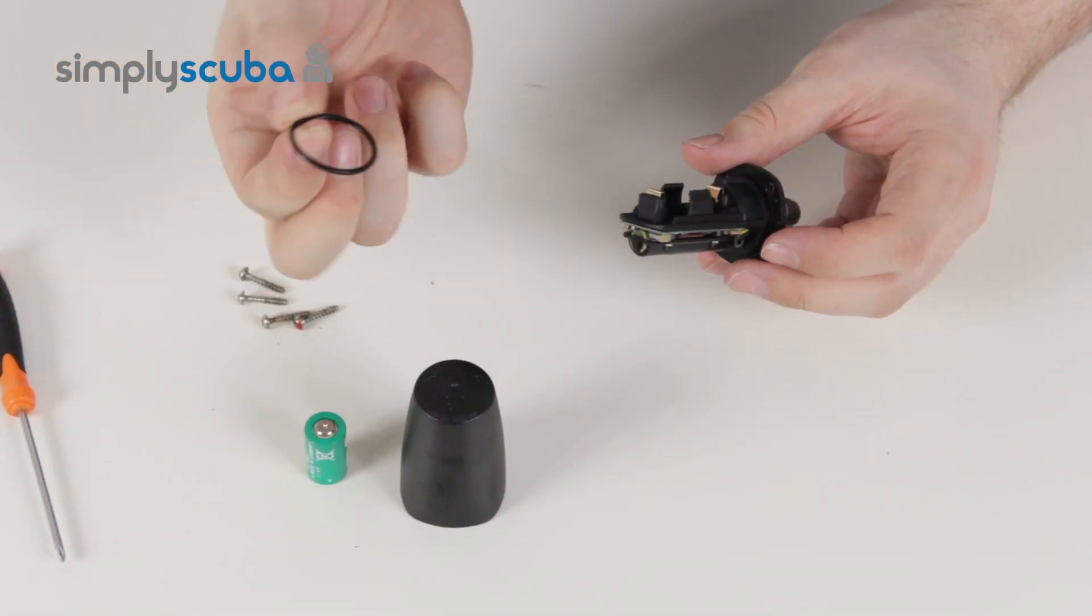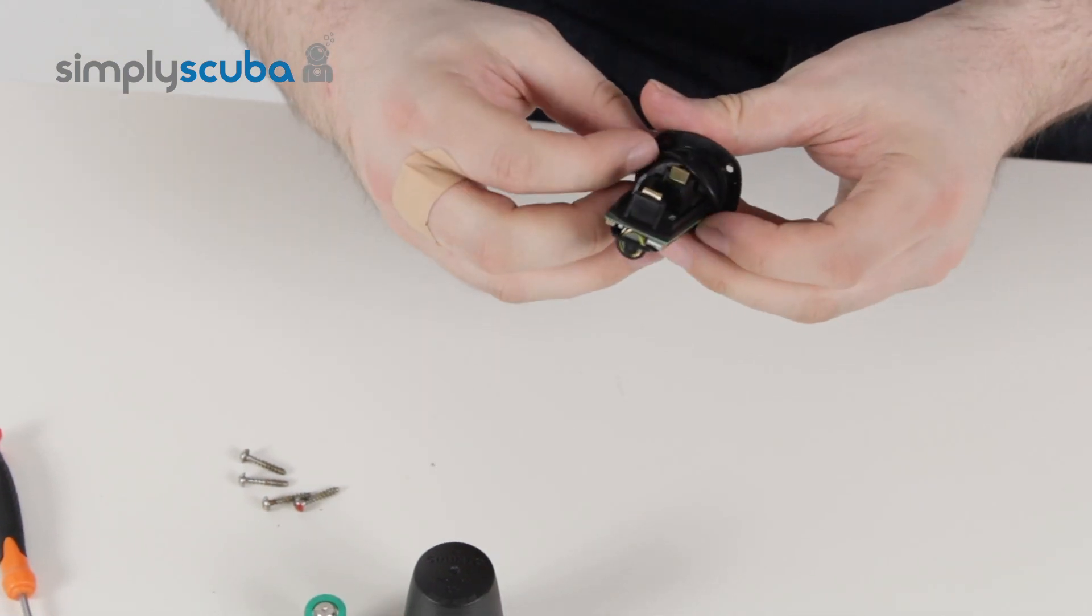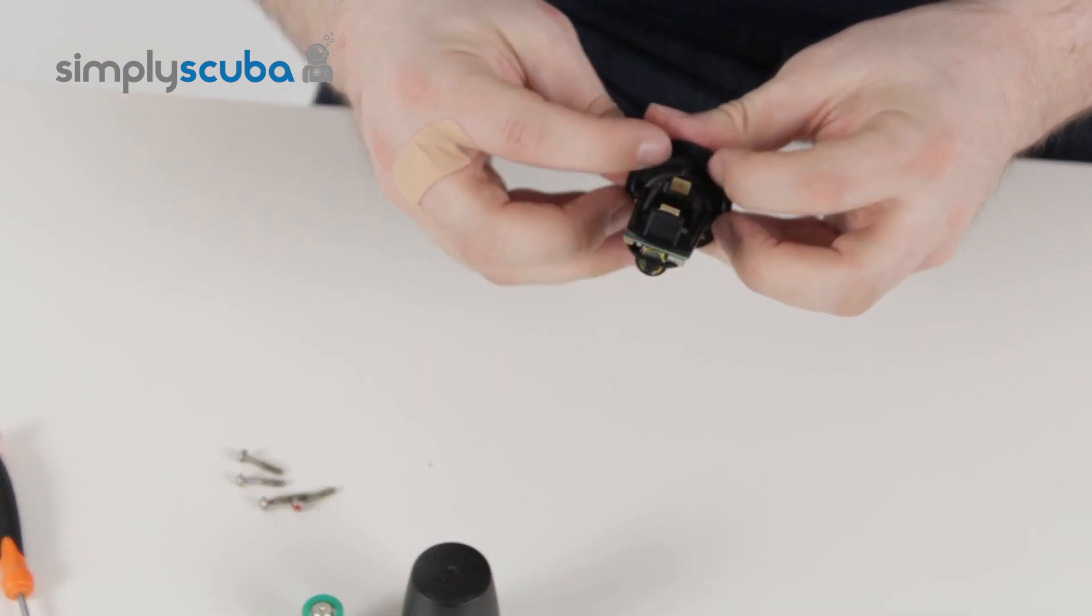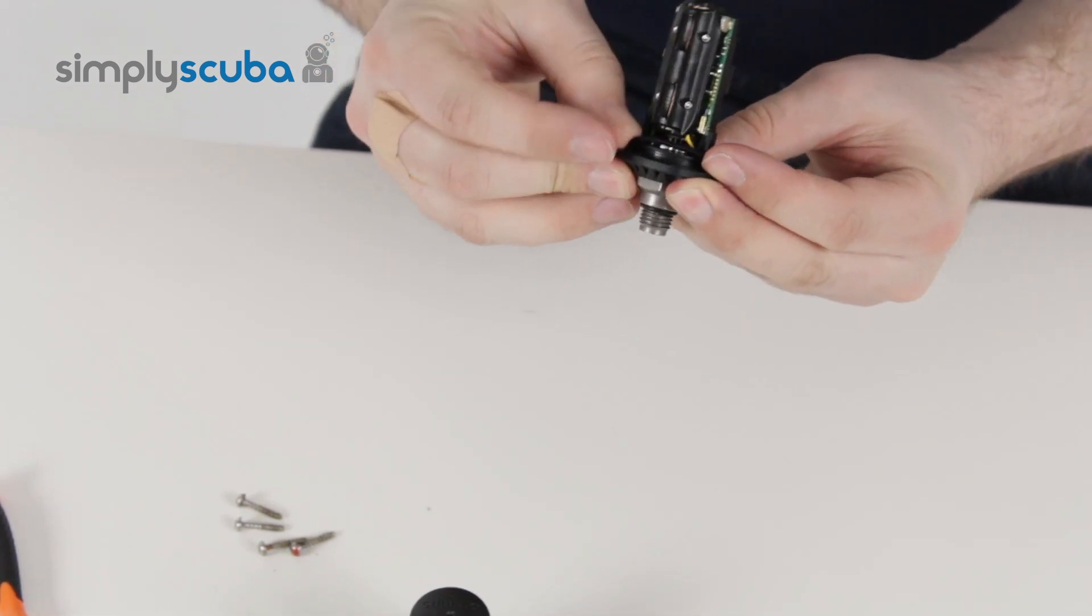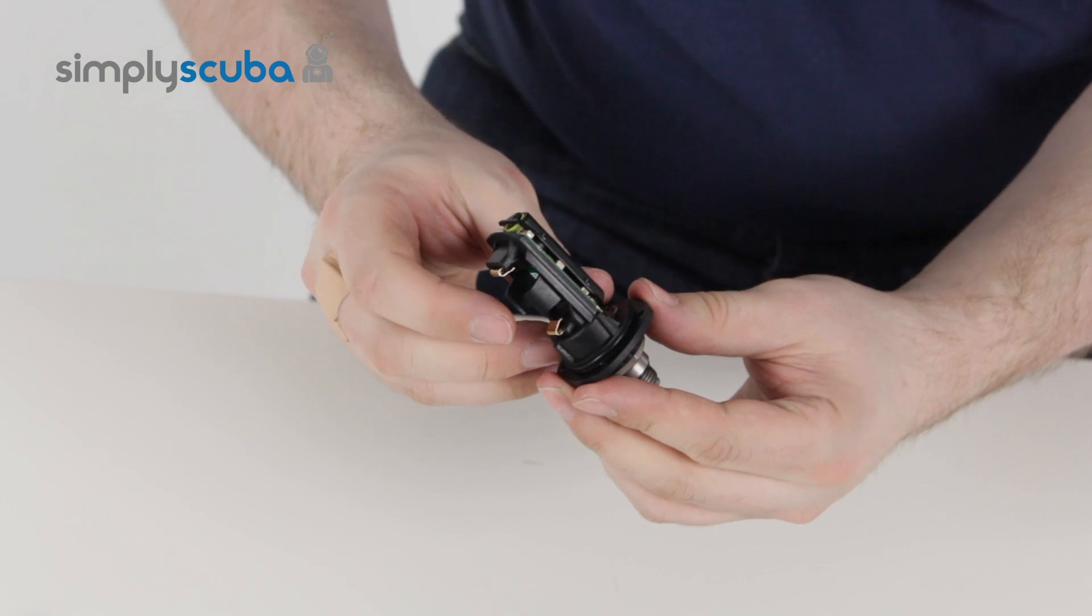The new o-ring, fit that. You don't need to lubricate this because it's a static o-ring, there's no movement in it. You just want to make sure that it's free from dust and dirt, and just fit that in nice and neatly, make sure it's nice and clean.